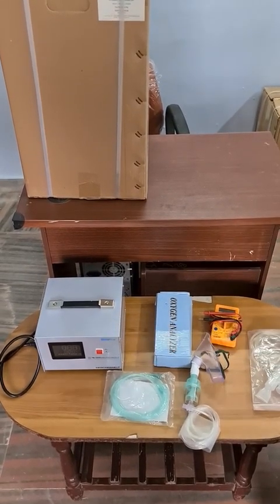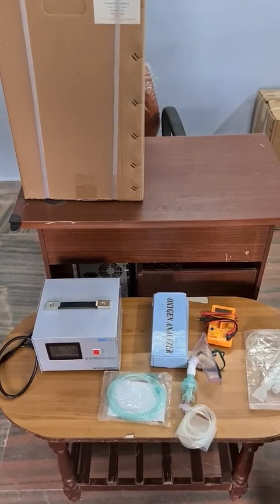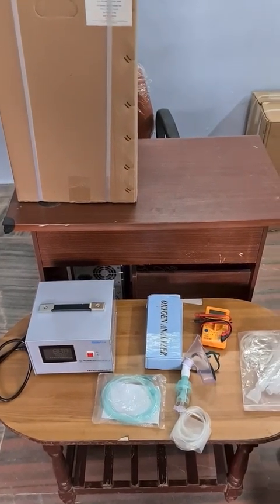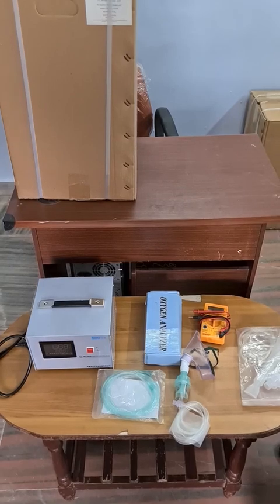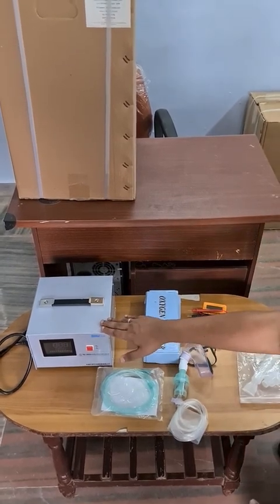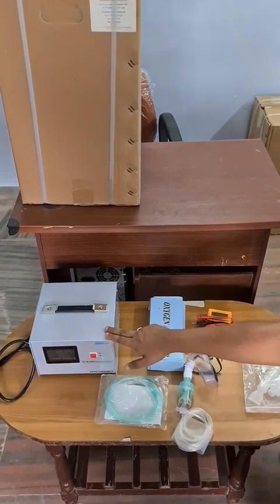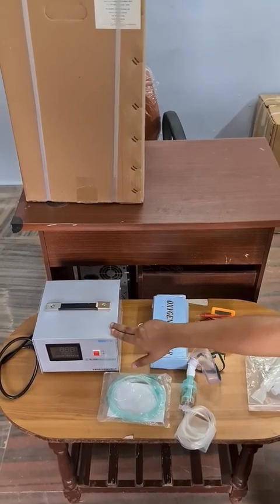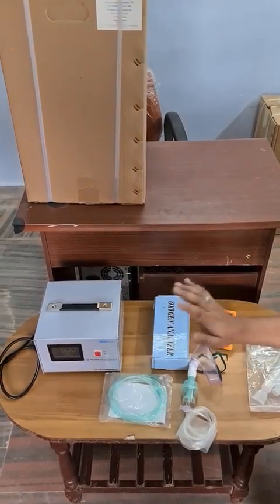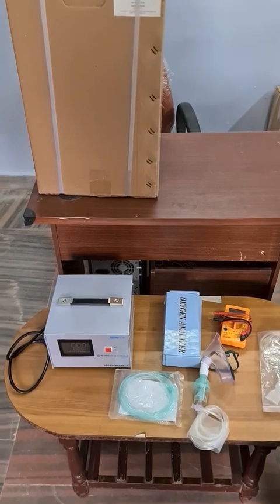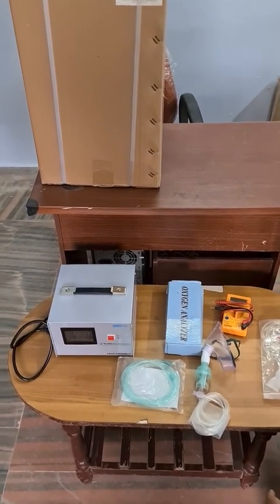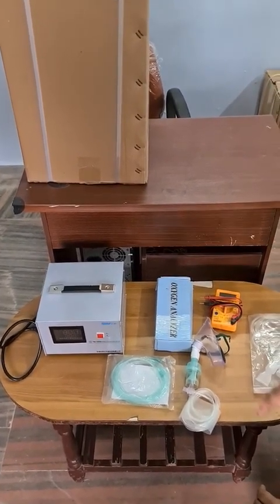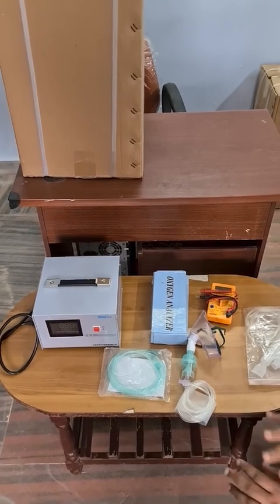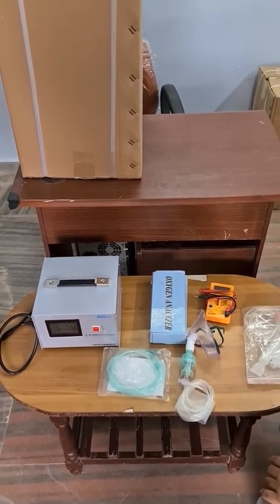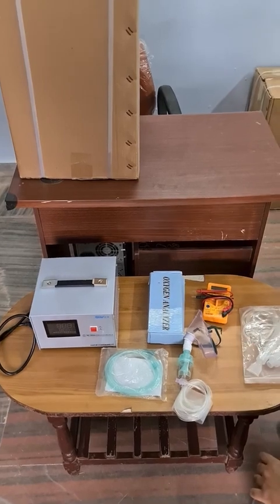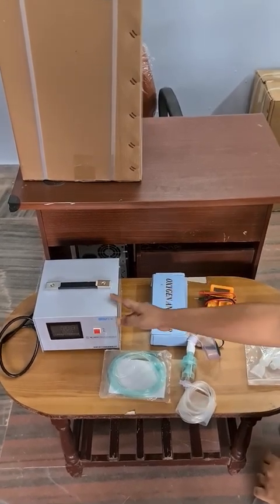Why we don't use the normal stabilizers which we use for TVs or fridges is that those stabilizers have a low kVA capacity, whereas these machines are designed for 1.5 kVA capacity. So whether you buy it from us or from outside, you should have a stabilizer with 1.5 kVA output if the voltage range is more than 230 volts at your location. If the voltage is already stabilized and you are getting 220 volts at your location, there is no need for an additional stabilizer.